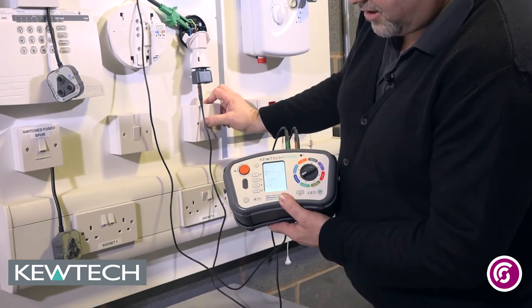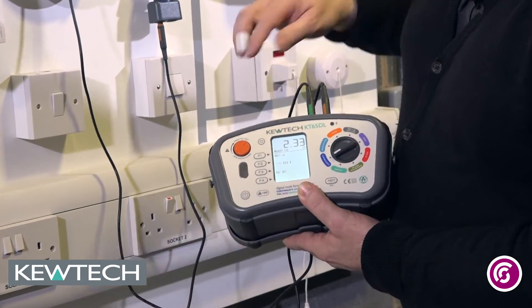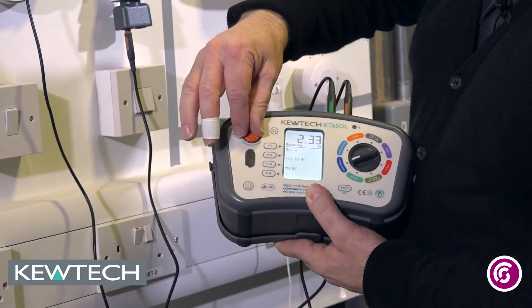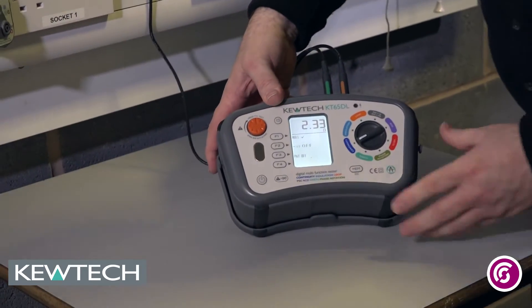I can do a functional check in continuity testing mode and I've got a value there of 2.33 ohms. I want to keep and store that value, so I push and twist the orange button out and I can actually store that value.